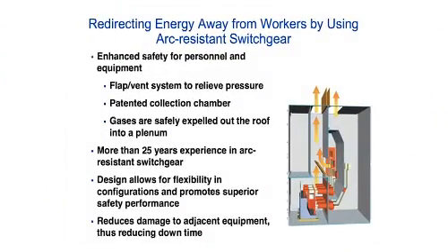In arc-res construction, the basic logic is that if a fault is occurring down here in the breaker compartment, it blows through. There's a flap that sits here, and you can see it here. Then it blows up through the top. The same thing is true in the bus compartment. There's normally a flap right here. It blows forward, and the gases go up the top into the plenum. In a cable compartment, they just vent straight to the top.